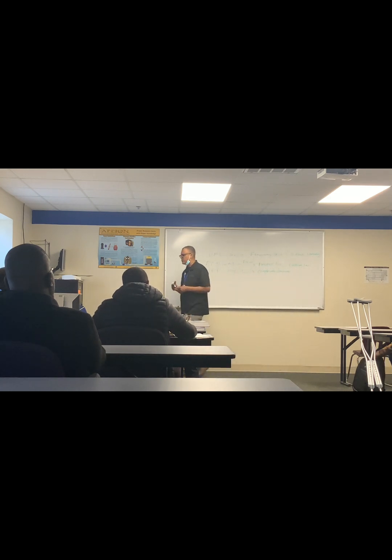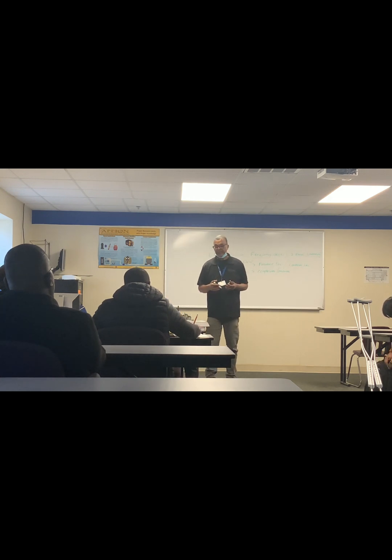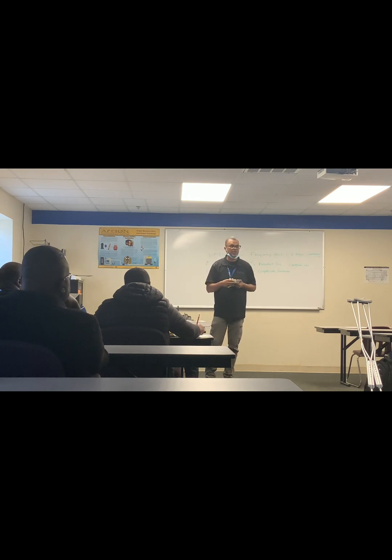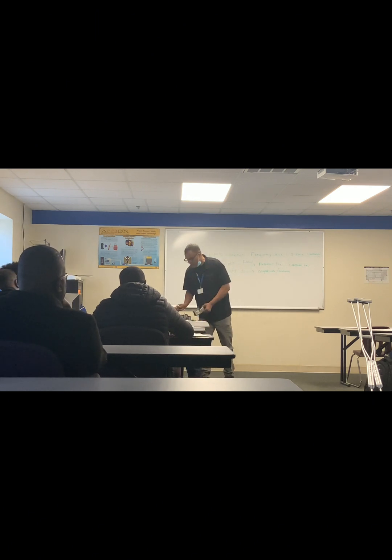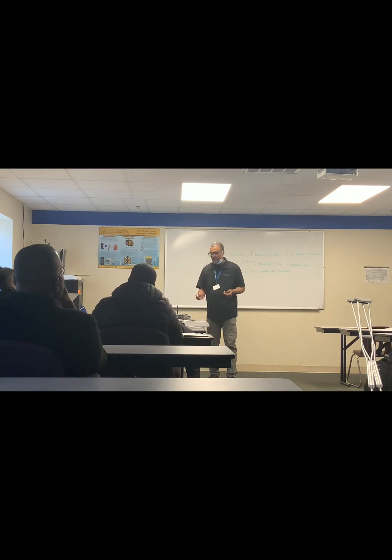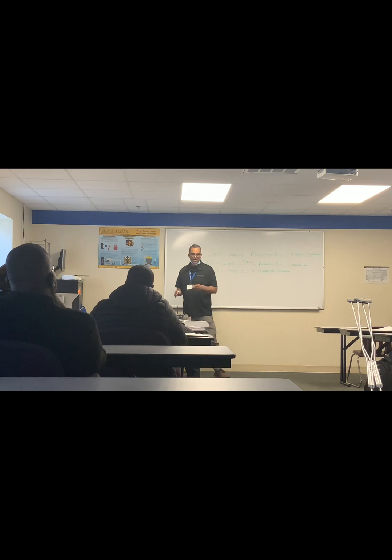It has been out for many, many years, and ECM, as we have learned, is a process of taking AC voltage and changing it through an electronic head. This is the electronic head. These are the low voltage connections on the lower part of the motor, and then the AC side will be on the top part of the motor connections.